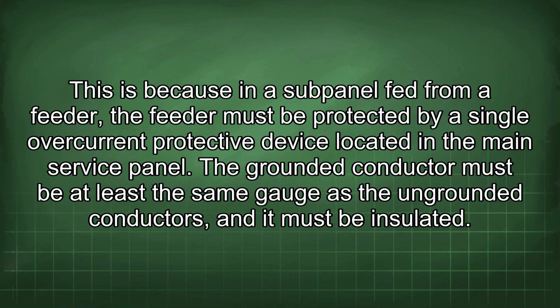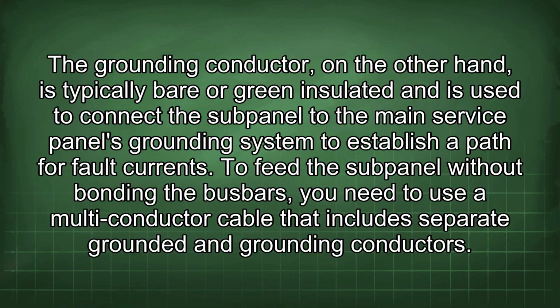The grounded conductor must be at least the same gauge as the ungrounded conductors, and it must be insulated. The grounding conductor, on the other hand, is typically bare or green insulated and is used to connect the subpanel to the main service panel's grounding system to establish a path for fault currents.